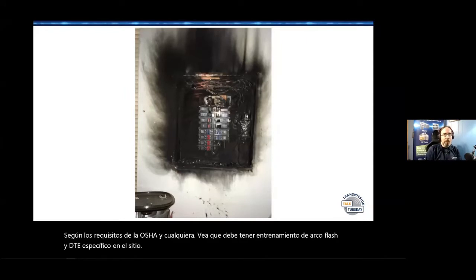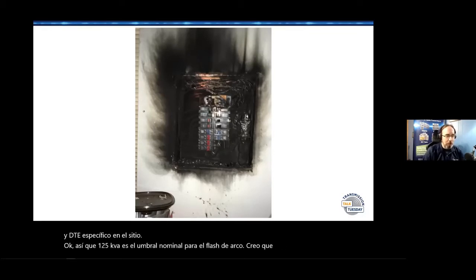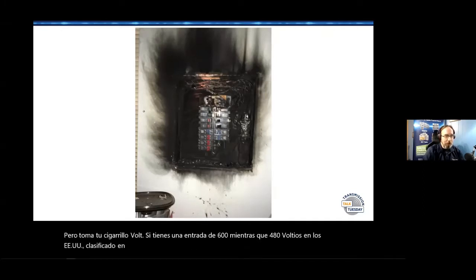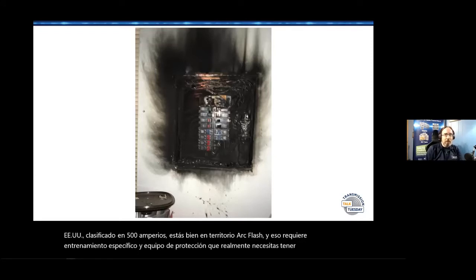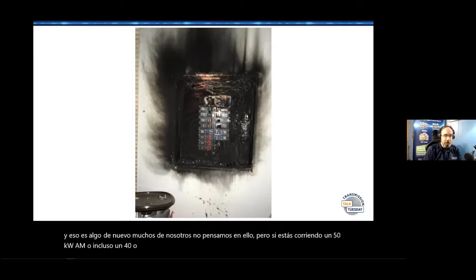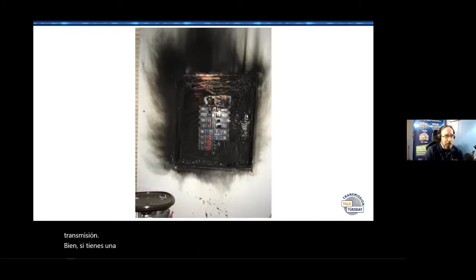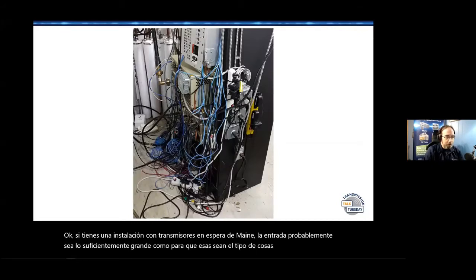So 125 kVA is the nominal threshold for arc flash, though I think it's 150 — I like to be a little cautious. Take your volts, so if you've got a 480 volt entrance in the US rated at 500 amps, you're well into arc flash territory, which requires specific training and protective equipment you need to be aware of. A lot of us don't think about this, but if you're running a 50 kilowatt AM or even a 40 or 60 kilowatt FM, you're in that territory on a broadcast site. If you've got a facility with main and standby transmitters, the entrance is probably sized big enough. So those are the kind of things you really want to pay attention to.